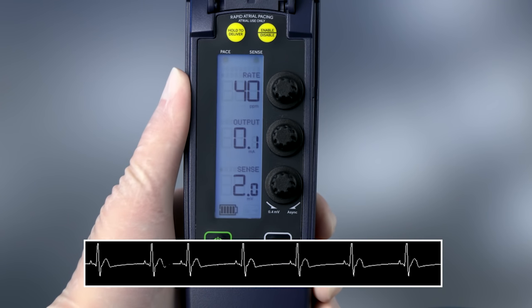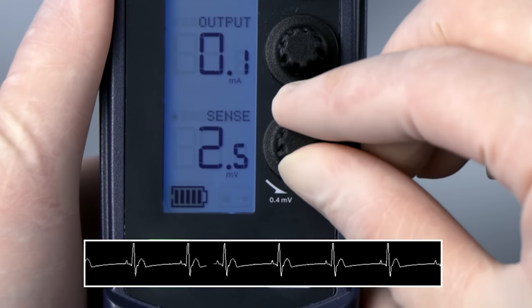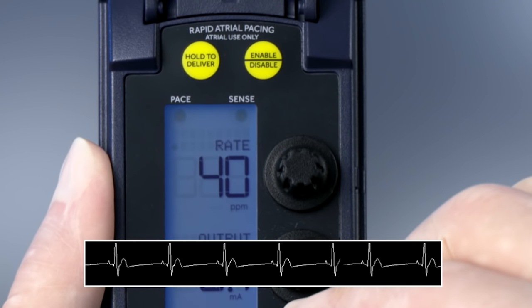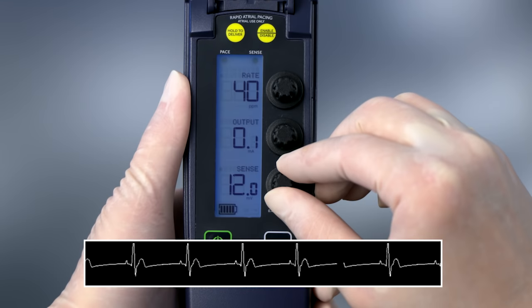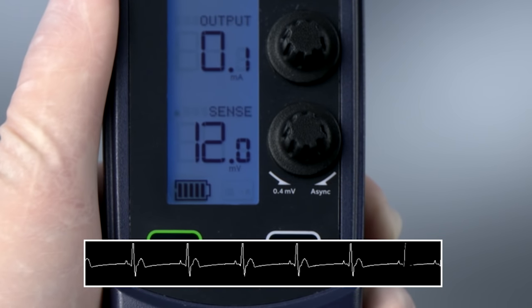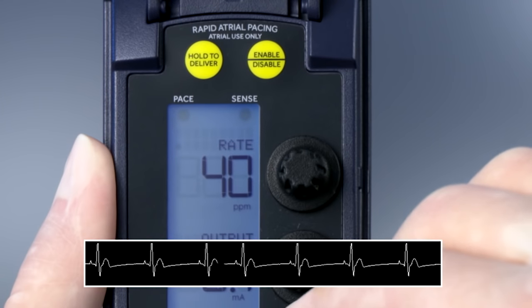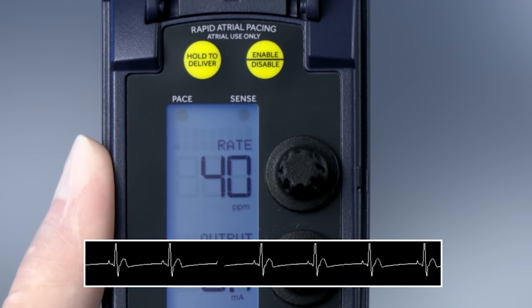Monitor the patient's ECG to ensure the sense indicator matches the device lights. Slowly turn the sensitivity dial clockwise, which increases the millivolt value, until the sense indicator stops flashing. The pace indicator flashes continuously, but capture is not likely because the output value is set to the minimum. Next, increase the sensitivity by slowly turning the dial counter-clockwise, which decreases the millivolt value, until the sense indicator starts flashing. The pace indicator then stops flashing. This is the atrial sensing threshold.